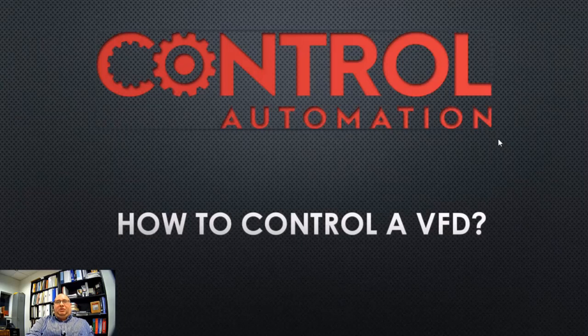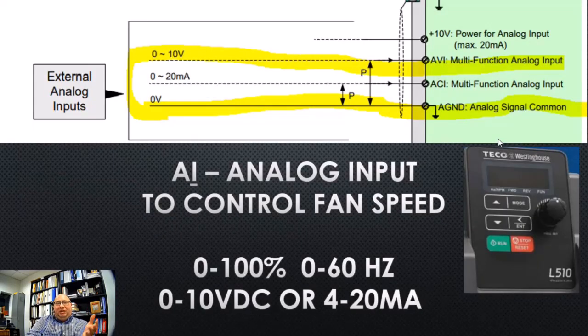Control and automation. How do we control a VFD? Absolutely, with control and automation. So we know how to start and stop, right? We start and stop it on the run forward command, but we also need an analog input to control the fan speed. Yes, you could do it in hand mode. You start, stop, run it in hand mode, and then you could dial up the potentiometer. That's one way to do it. But we would also want to have a little bit more control from an external source.